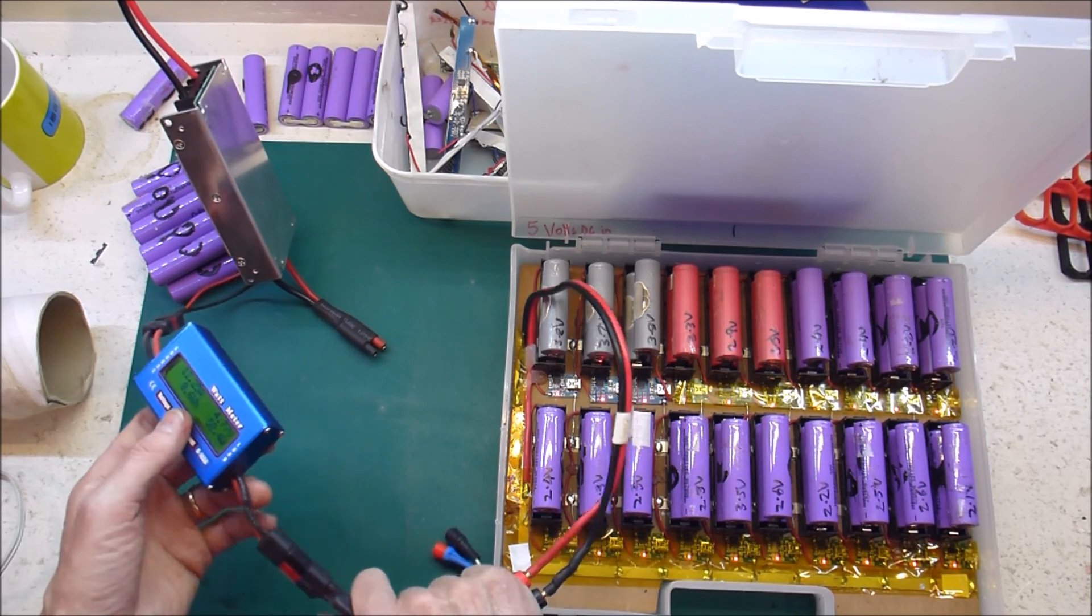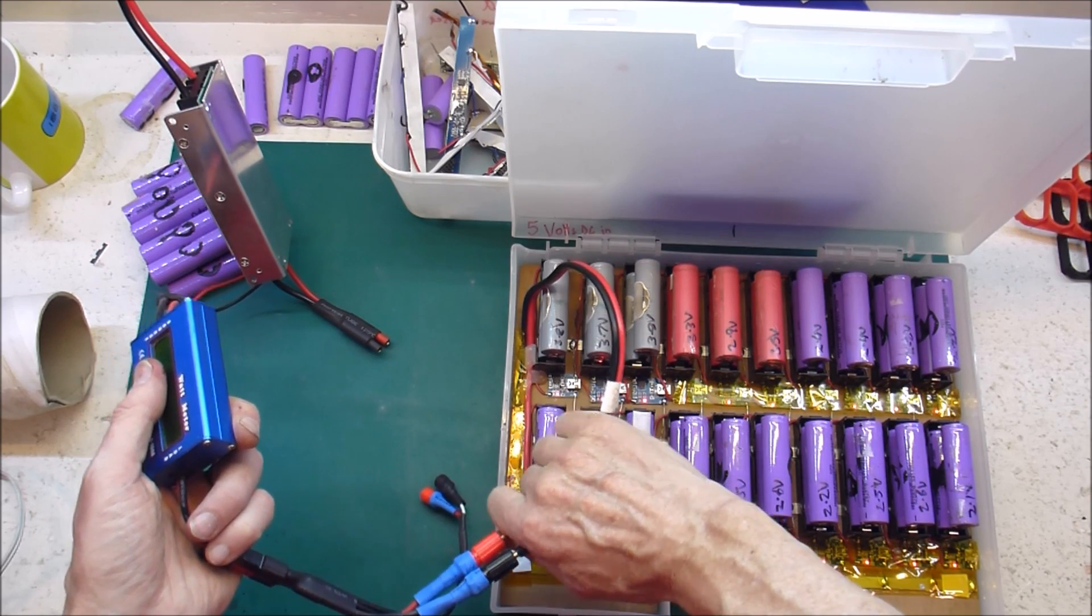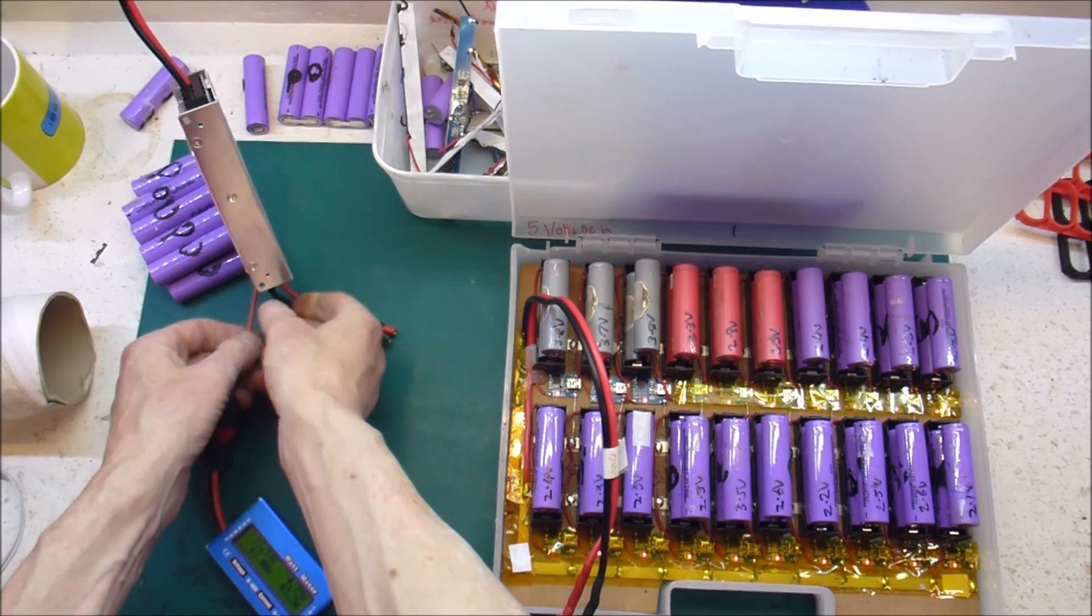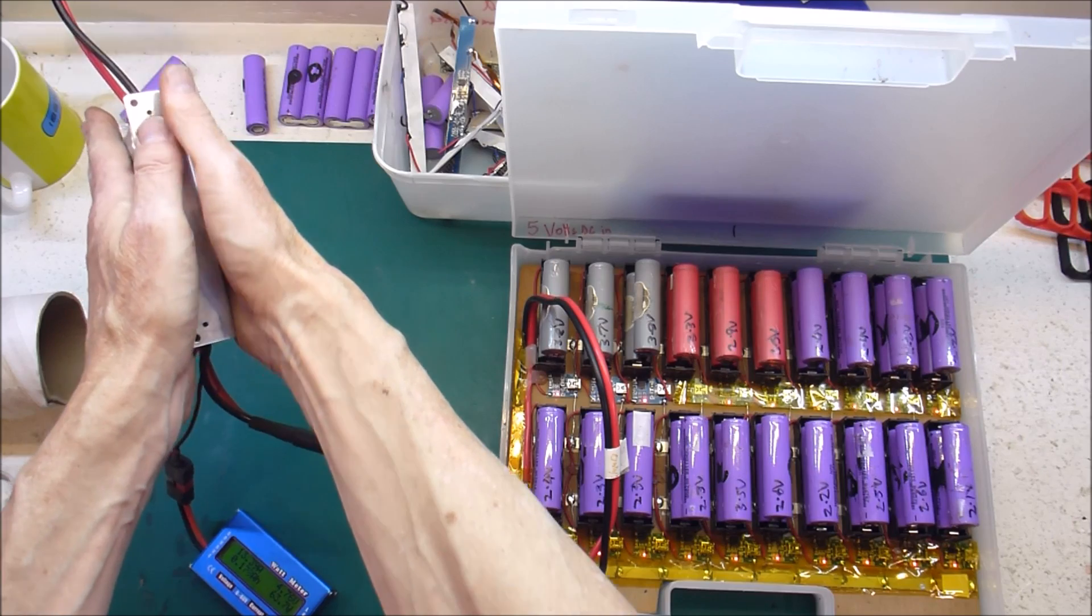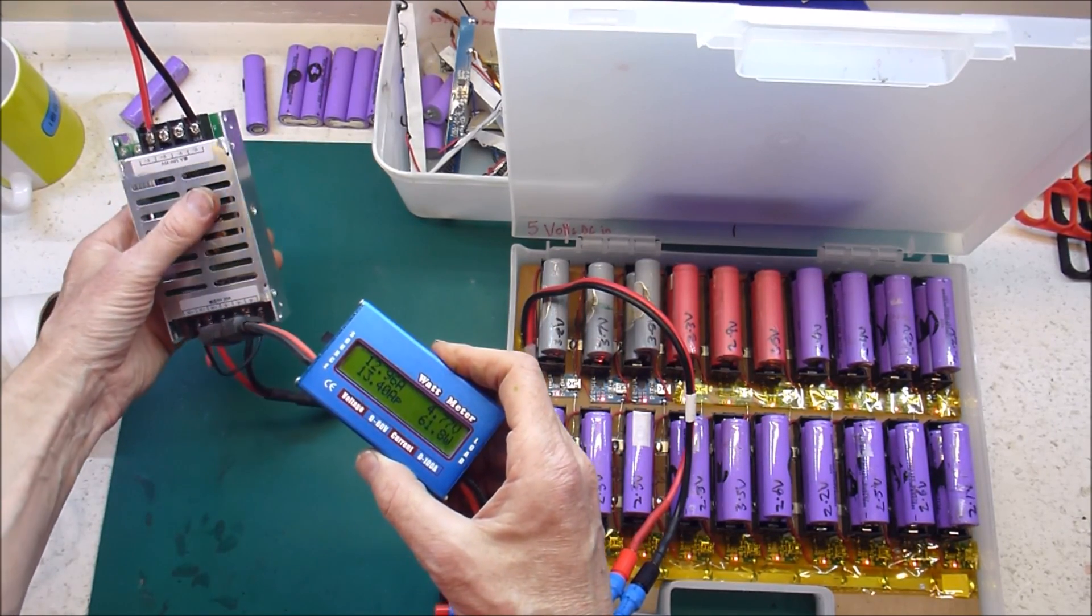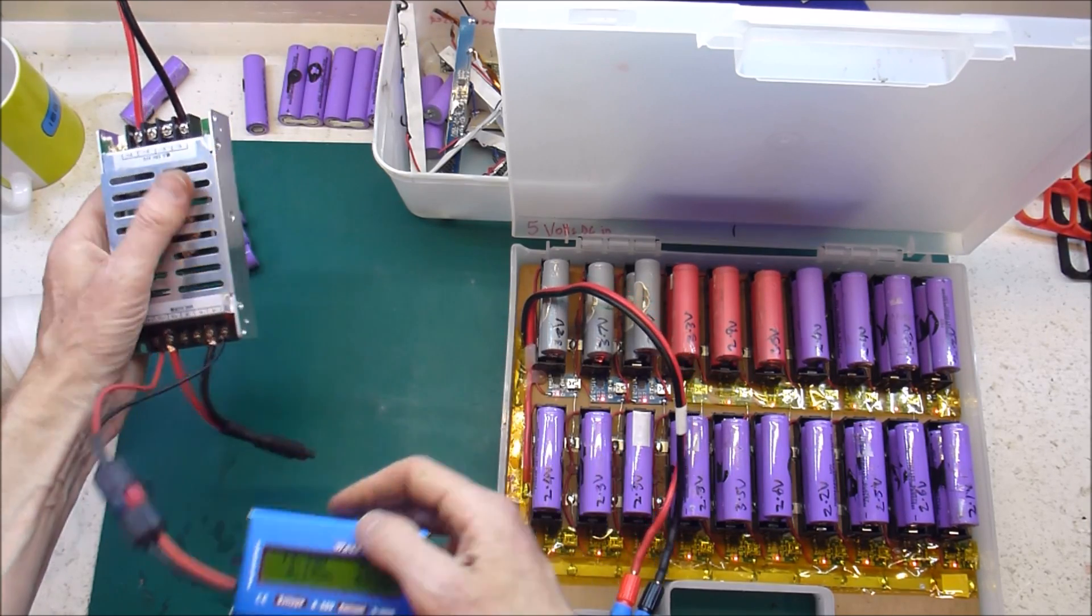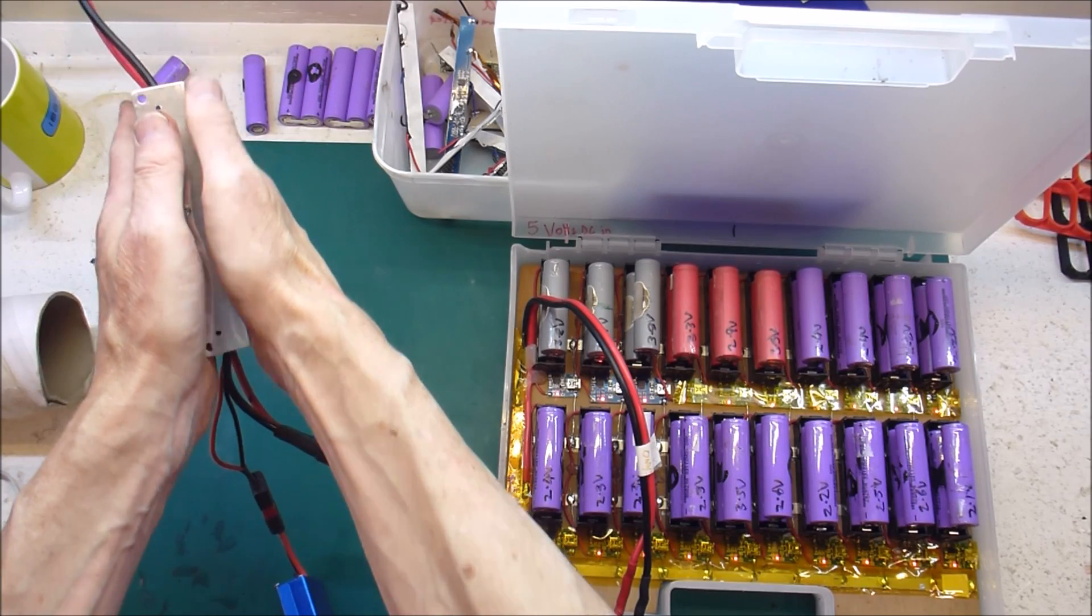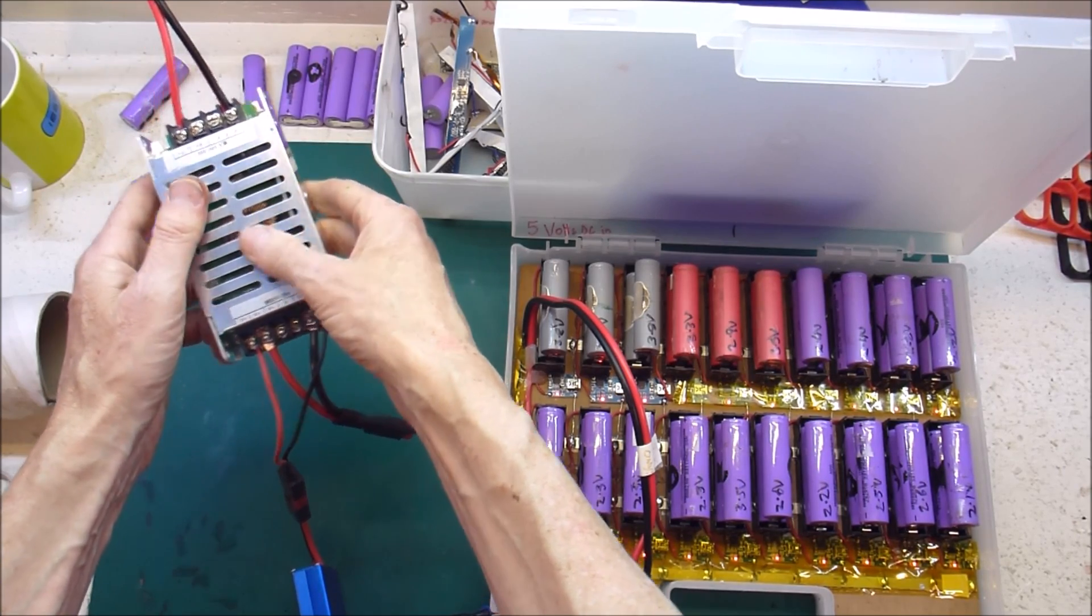The other thing that was happening, I just recently checked all this. This is getting kind of warm. A little bit earlier, before I turned the camera on, it was running at 14.5 amps and this was getting to the point where I was starting to not want to hold onto it, which is usually a bad sign.